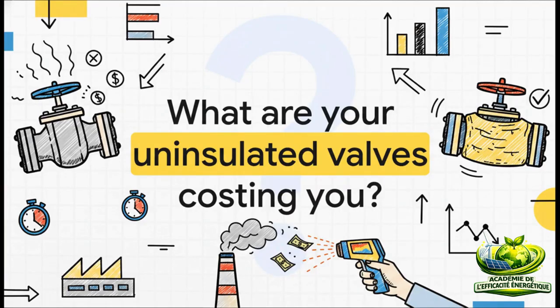What are your uninsulated valves and your unchecked excess air costing your facility right this very minute? Seriously, grab a thermal gun, go check your boiler stacks, and just do the math. Because every single day you wait to implement these fixes is just more of your budget sent straight out the exhaust pipe. Get out there, optimize your system, and take control of your energy costs.